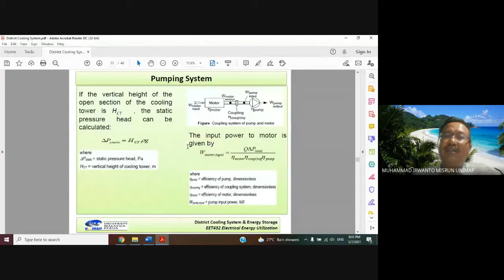This depends on the flow rate. Then, to find the friction of the fittings, we use the loss coefficient C0, which can be obtained from this table. Follow it according to the type of fitting. For an elbow, for example a 90 degree long elbow, it depends on the inner diameter. Let's say 80, it is here: for the 90 degree long elbow, C0 is 0.25. For a gate valve, we follow across to the valve, and its C0 is 0.22.